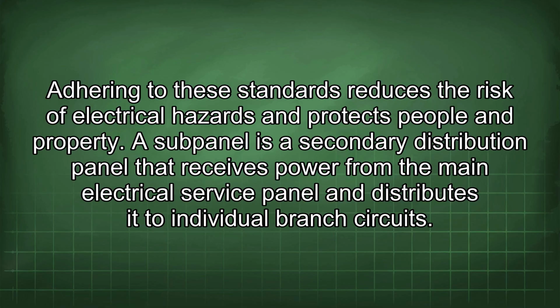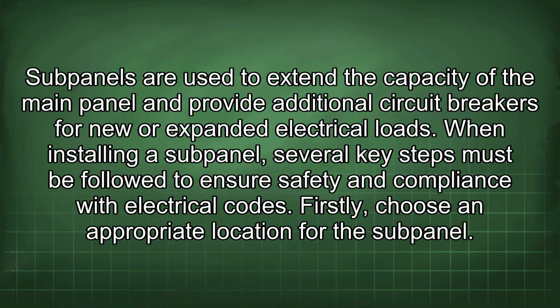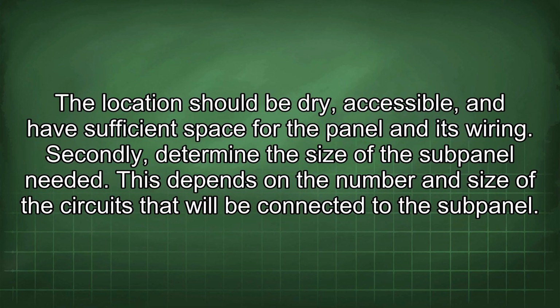A subpanel is a secondary distribution panel that receives power from the main electrical service panel and distributes it to individual branch circuits. Subpanels are used to extend the capacity of the main panel and provide additional circuit breakers for new or expanded electrical loads. When installing a subpanel, several key steps must be followed to ensure safety and compliance with electrical codes. Firstly, choose an appropriate location for the subpanel. The location should be dry, accessible, and have sufficient space for the panel and its wiring.